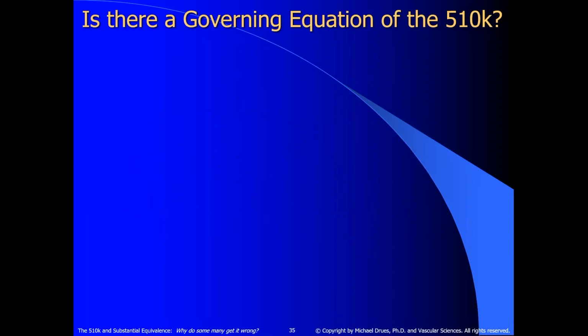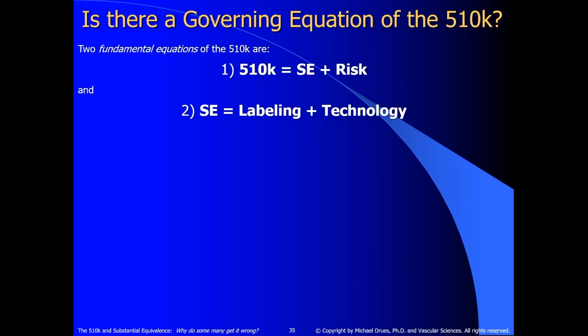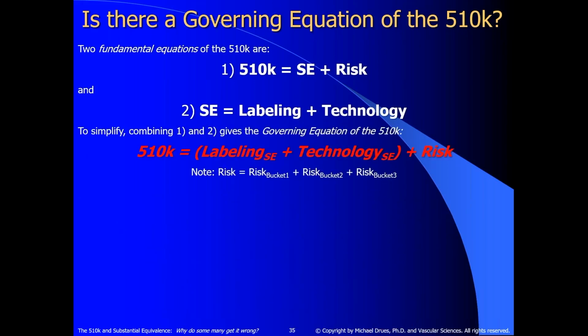Getting into a little bit more detail, what goes into a successful 510K? Is there a governing equation of the 510K? Well, coming from an engineering background, I like to think analytically. So there are two fundamental equations of the 510K. First of all, the 510K is based on substantial equivalence and risk. And then the second is substantial equivalence is equal to labeling and technology. So if we substitute equation 2 into equation 1, we get what I call the governing equation of the 510K. Basically, a successful 510K means you have to solve this equation: labeling, technology, and risk.